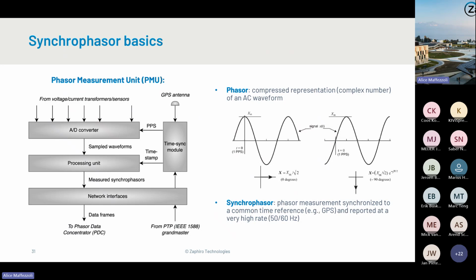PMU is a phasor measurement unit. A phasor is the complete information of a waveform, so not just amplitude, but also phase and frequency. We do this measurement at a very high speed rate, every 20 milliseconds, and these measurements are time synchronized, for example with a GPS antenna, using a GPS signal.